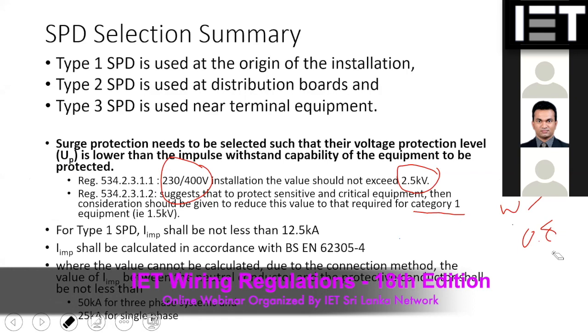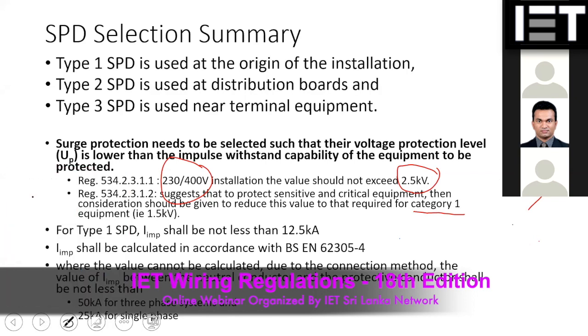So the UP value should be less than or equal to 0.8 times UW. UW is your insulation level. Depending on the category of your equipment, you can find out what the insulation level is, whether it is 800 volts, 1.5 kilovolts, 2.5 kilovolts, 4 kilovolts or 6 kilovolts. There are different categories of equipment, and depending on that, you have to select your surge protective devices.